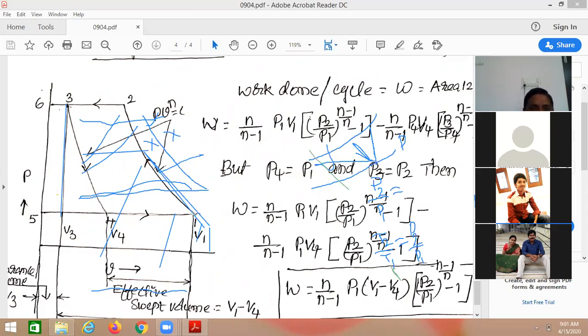Here also 1, 2, 3 is the compression stroke starting from 1. This is the end of the suction stroke, where air has entered with the state point of V1 and temperature of T1, and got compressed during the compression stroke up to point 2. At the end of point 2, the delivery valve opens and the compressed air is pushed out of the cylinder up to point 3. Beyond the clearance volume, the piston won't move. So the piston has to move back starting from the limiting volume corresponding to 3. From there the suction stroke will commence.